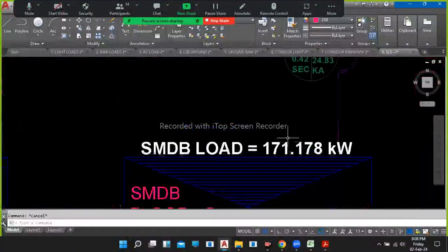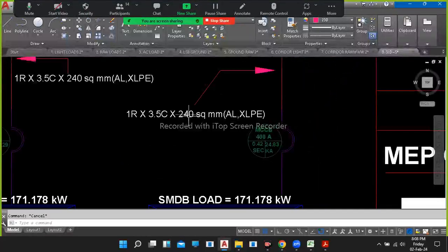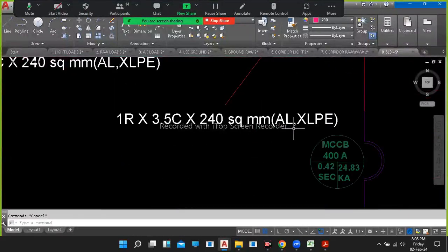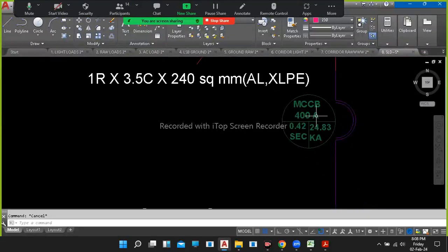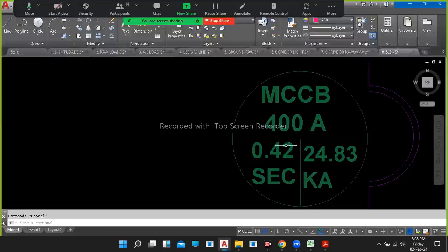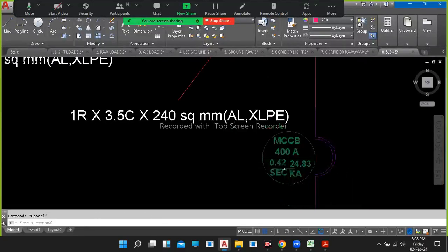Then for this SMDB load, again cable size calculation, he got 103.56, 240 square mm AL XLPE. Okay, single run 3.5 core 240 square mm. Okay, AL XLPE, and the MCCB he got 400 amps with the fault current as 24.83 kiloamps, and the tripping time is 0.42 seconds.